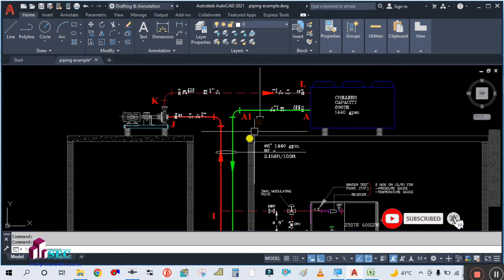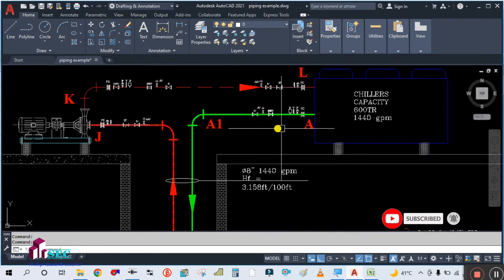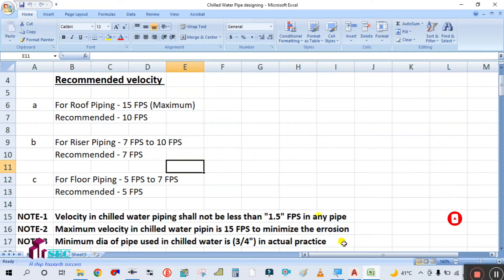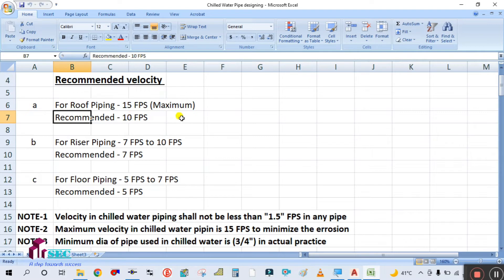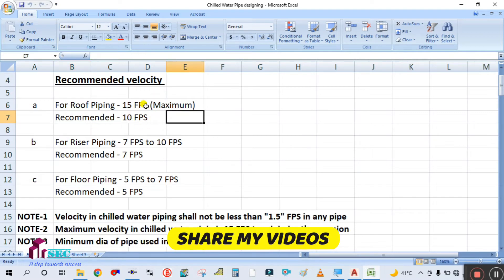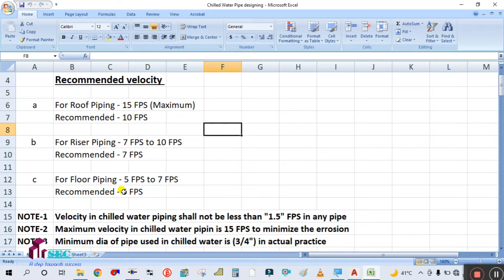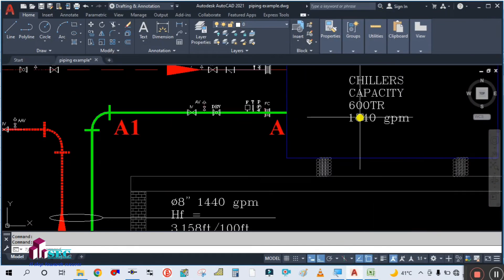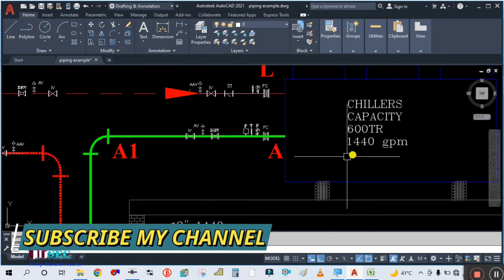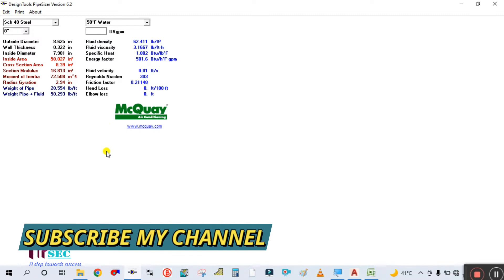So what will be the pipe size for this? For the roof piping, the recommended velocity is 10 feet per second and the maximum is 15. You have to calculate the pipe size using the pipe sizer by checking the velocity. The GPM here is 1440.